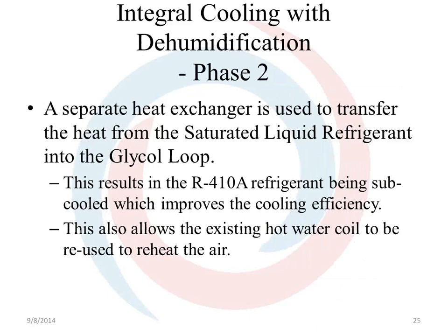What Xcelon does is that they reuse the hot water coil to minimize the internal static pressure drop. And as an added benefit, by using the heat exchanger to transfer heat from the saturated liquid refrigerant to the glycol loop, we subcool the liquid refrigerant, which increases the cooling SEER. Now when this is introduced, they'll have this up to 40 pounds.